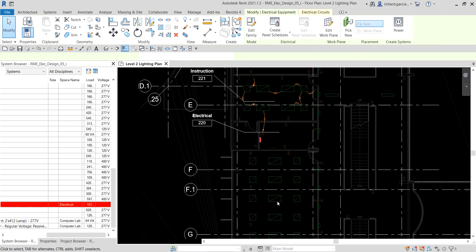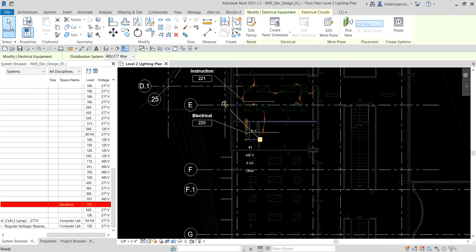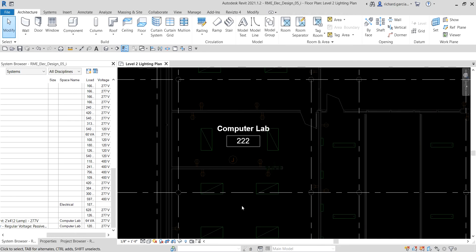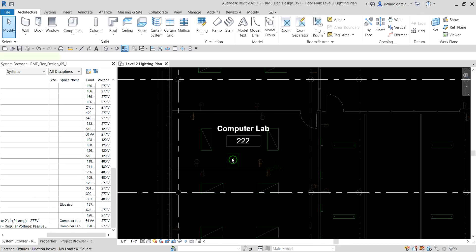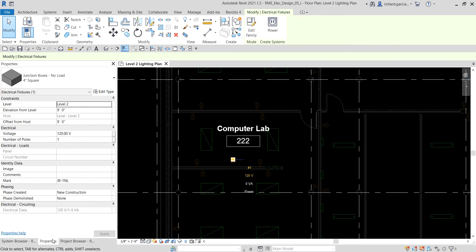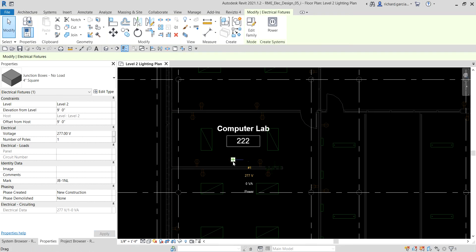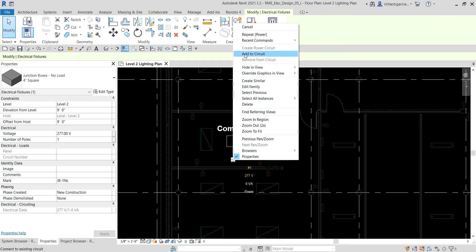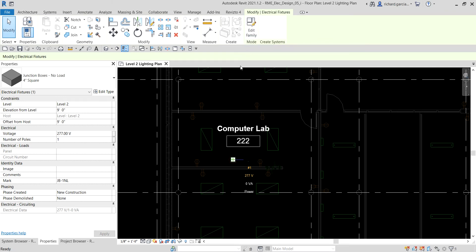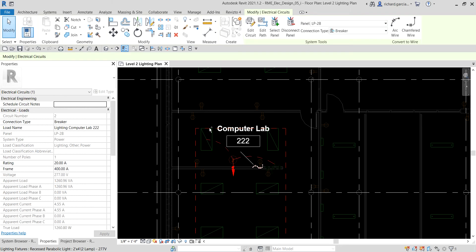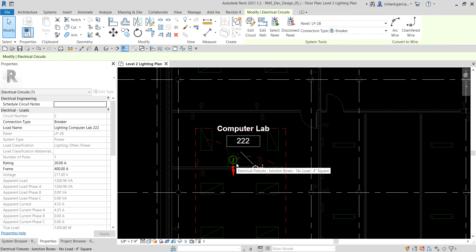Now I want to add more lighting fixtures to my system. Going back to the 222 space, I'll select this junction box. From Properties I want to change the voltage from 120 to 277 and press Enter. While it's still selected, I'll right-click and select 'Add to Circuit,' then select one of the elements already part of circuit number two — that lighting fixture — and the junction will now be part of that circuit.